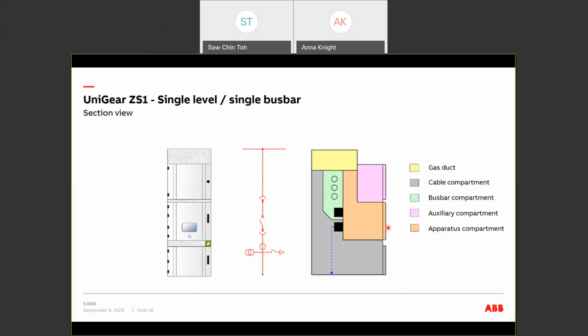This slide shows the typical sectional view of the UniGear ZS1 cubicle. The LV compartment will house the protection relay and auxiliary equipment. The apparatus compartment is where we put the withdrawable circuit breakers or contactors. The CTs, the VTs, and the cable termination are all mounted in the cable compartment. This is the typical panel showing the cable coming from the bottom.